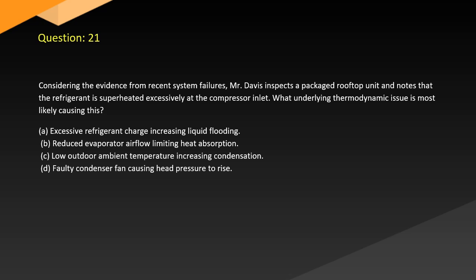Question 21. Considering the evidence from recent system failures, Mr. Davis inspects a packaged rooftop unit and notes that the refrigerant is superheated excessively at the compressor inlet. What underlying thermodynamic issue is most likely causing this? A. Excessive refrigerant charge increasing liquid flooding. B. Reduced evaporator airflow limiting heat absorption. C. Low outdoor ambient temperature increasing condensation. D. Faulty condenser fan causing head pressure to rise.